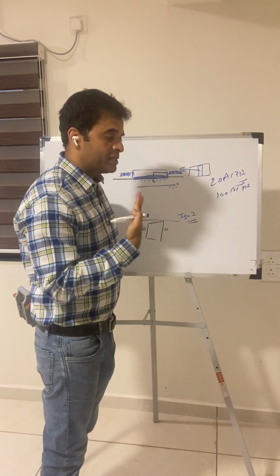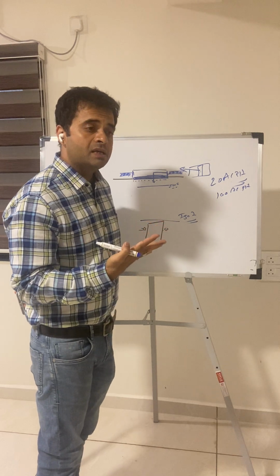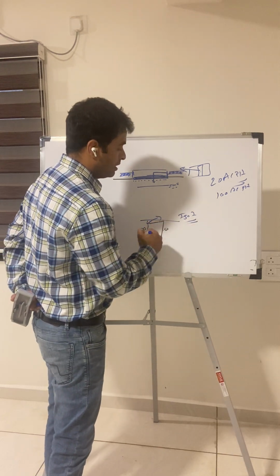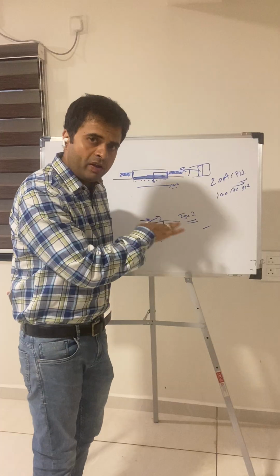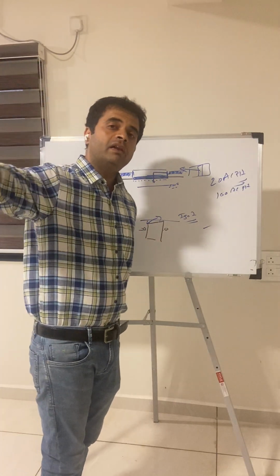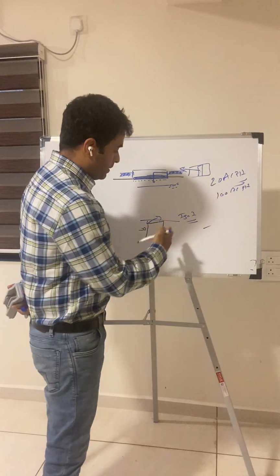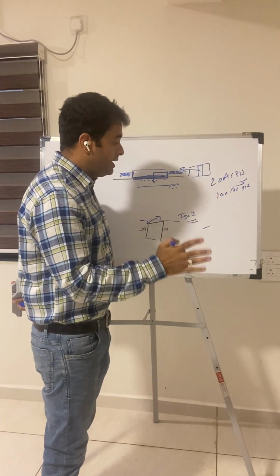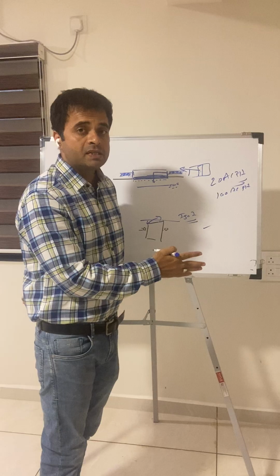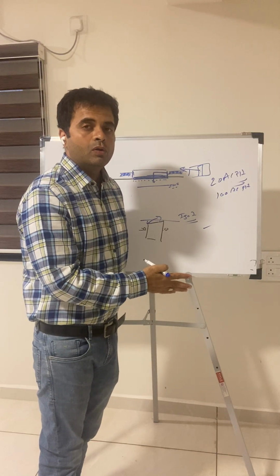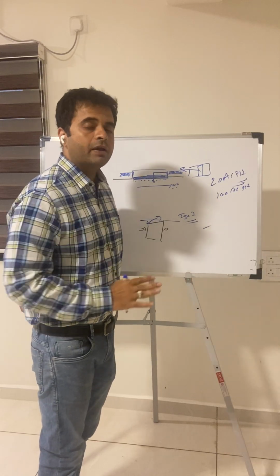For me, validation reports hold good only when there are fewer particles at the table level, at the peripheral level. Here people are moving around, not going to the ceiling level and then doing operations. No, people are around at the table level. So I need to have a classification of ISO 7 and 6 at the table level. So all my projects I design in the same way.